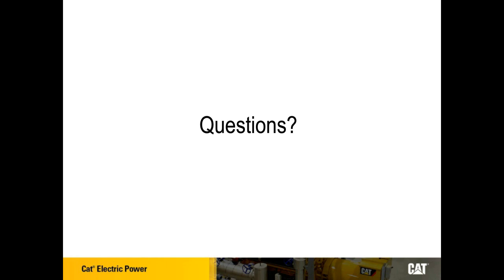I think this is certainly a place we've got some experience in recently. When you speak microgrid, it's an application where utility power isn't usually common, so we've typically seen it in island or remote applications. Usually in those locations natural gas isn't available, so diesel fuel has mostly been used for microgrid applications. But when you're running a generator set for a long period of time like in a microgrid application, to reduce overall runtime and operating costs, natural gas would be preferred, and you can also avoid some fuel delivery problems. It just usually isn't an option we typically see in remote microgrid applications.